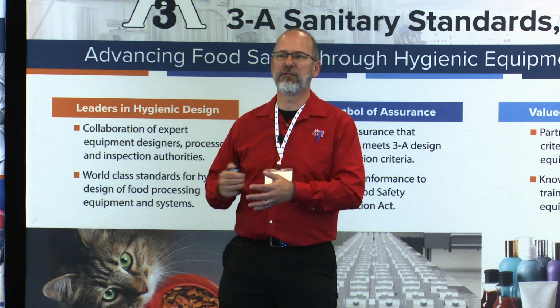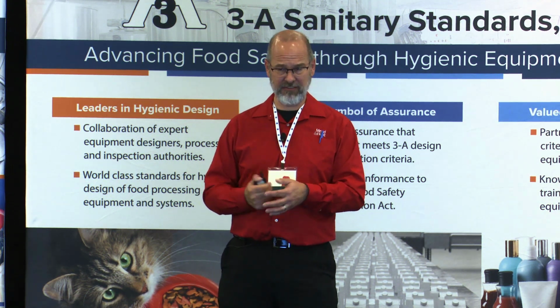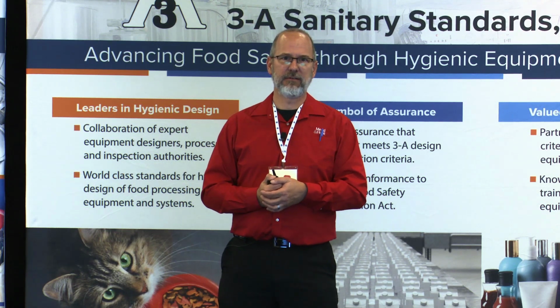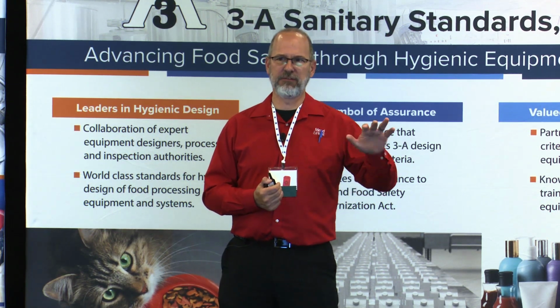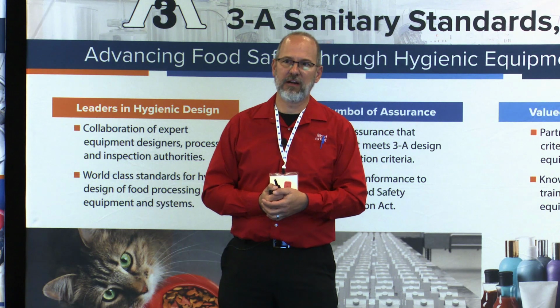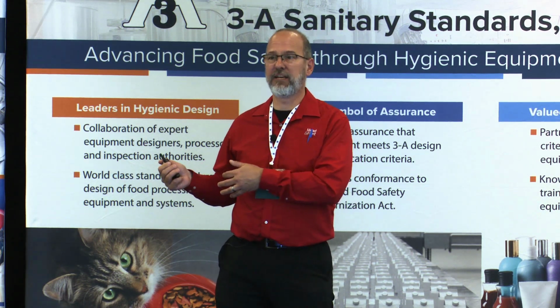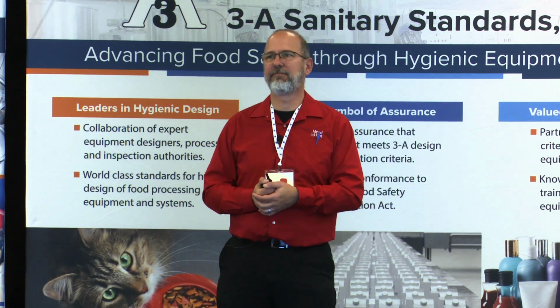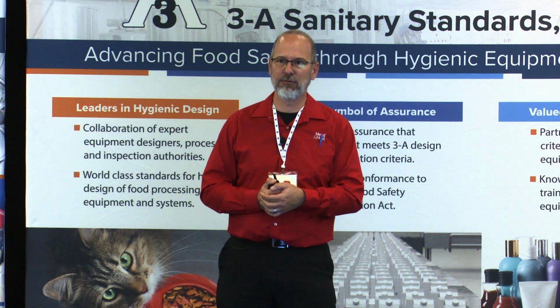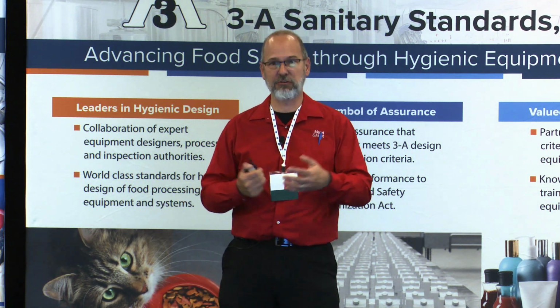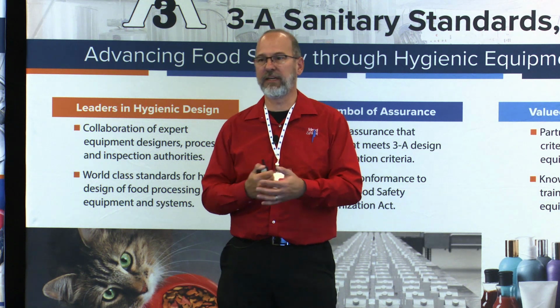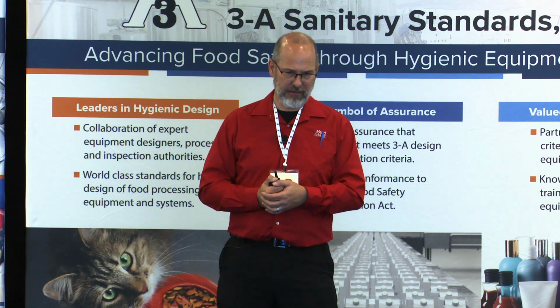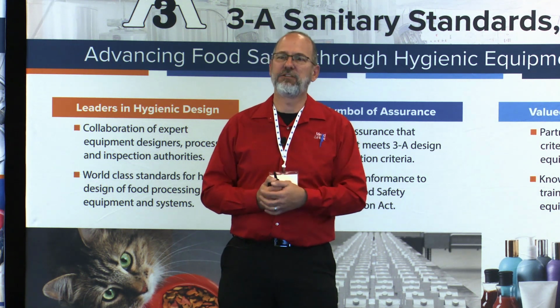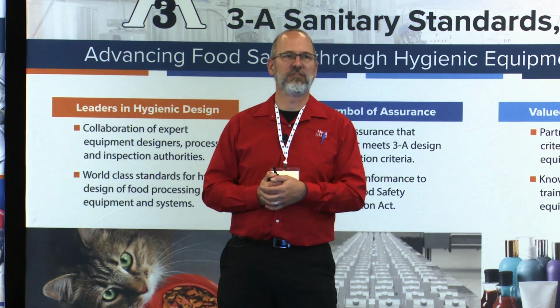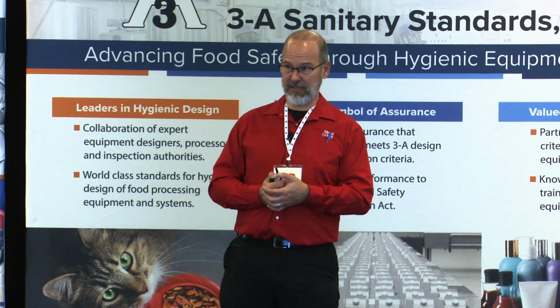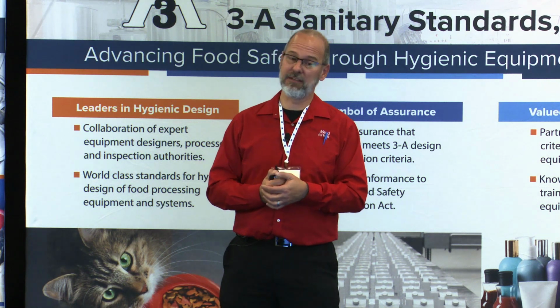We've kind of steered away from that. We don't do that as much anymore. We'll use it as a back check, but the two concepts of doing precise load calculations to figure out how much air you need in a room and using a flat air change rate don't typically align. You don't normally do an air change rate calculation. It just turns out to be 12 air changes an hour or 20. It's some value. If you just size for a flat air change rate, you could end up significantly oversizing the system and making it way bigger than it needs to be and spending a lot more money than you need to.